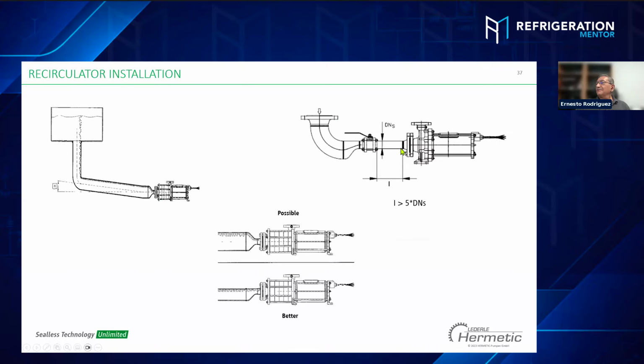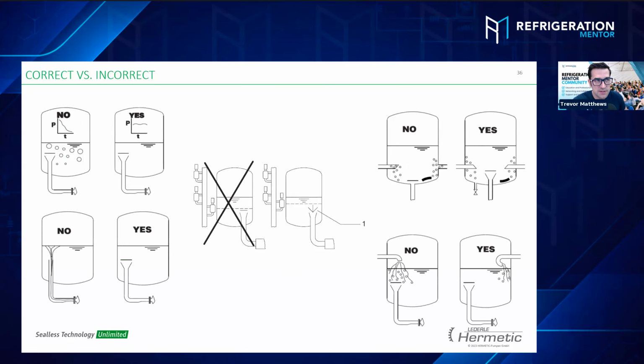Okay, normally when you have a valve installed close to the pump, before we go ahead, that differential pressure regulating valve that you said, for example, was set to 45 psi. The purpose of that is that if our pressure differential gets higher than 45, we want to bypass so we don't cause fluctuation in our evaporators. Is that correct? Yes, okay.